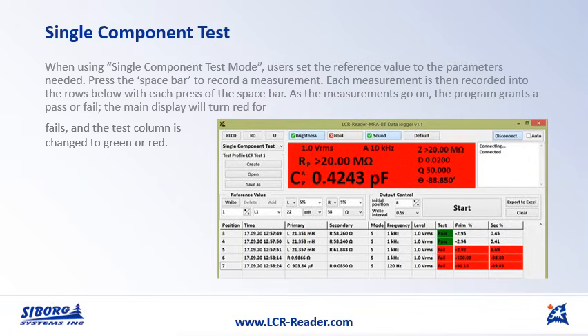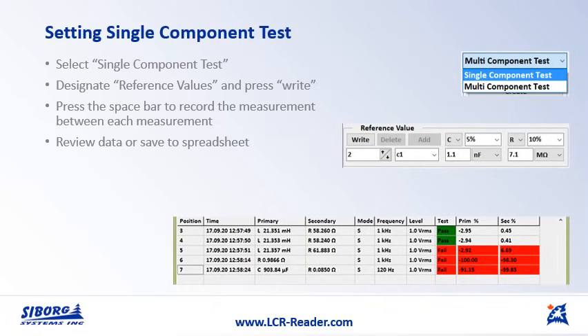For a single component test, you basically just measure the component once you define it, and then if you press the space bar, it gives you the component measurements and saves it in a spreadsheet. When you specify single component, you select single component, define reference values, and press on write to write them. Then when you press the space bar, you record the measurement into the spreadsheet again.